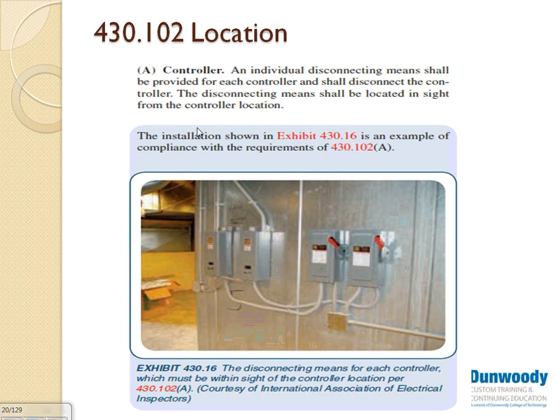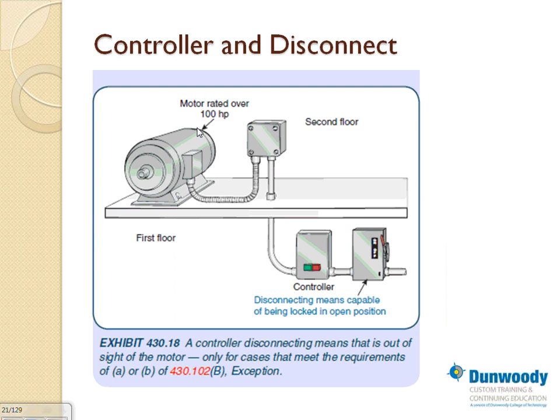Any comments, guys, about the disconnect? A disconnect can range from a snap switch on the wall for smaller motors, into big circuit breakers in an MCC, into a NEMA heavy duty disconnect on the wall like this, into a plug for certain motors. The plug itself is rated as a disconnect. You can plug the machine on and off for smaller equipment. So a couple of pieces of equipment.